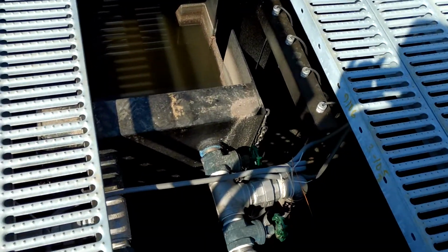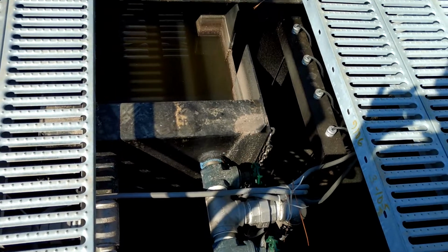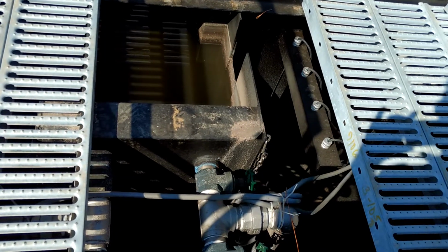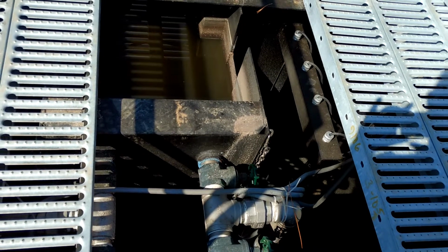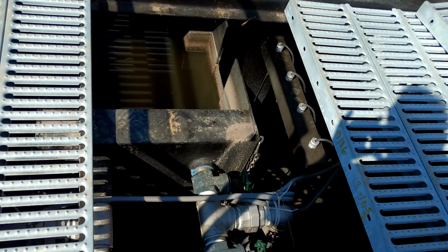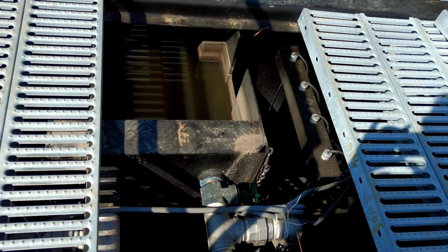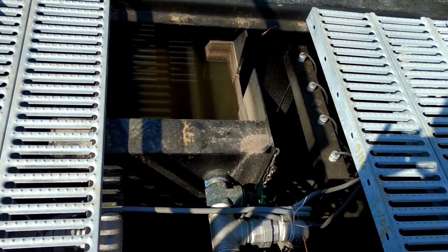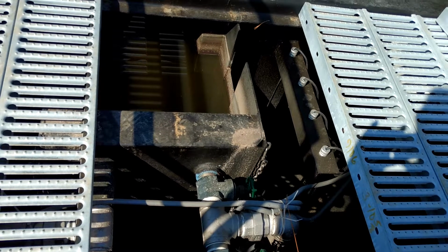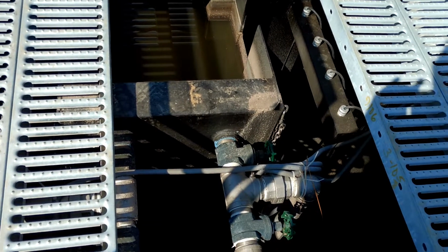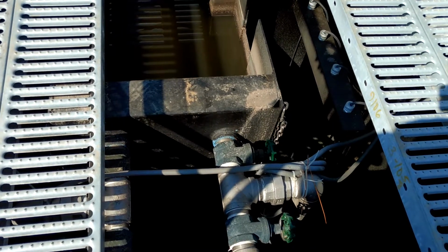This first tank is the flow equalization chamber. And again, the purpose of the flow equalization chamber is to even out the flows to the treatment plant so that the downstream processes are fed throughout the day rather than have large hydraulic flows which can overload the treatment plant.